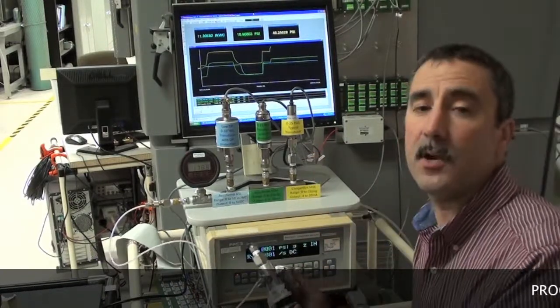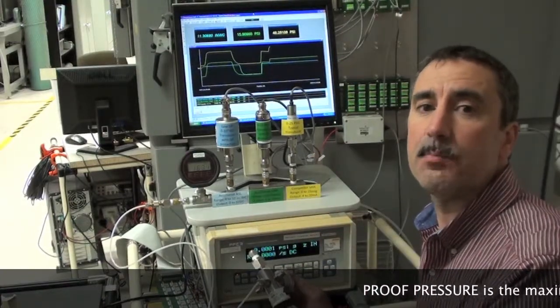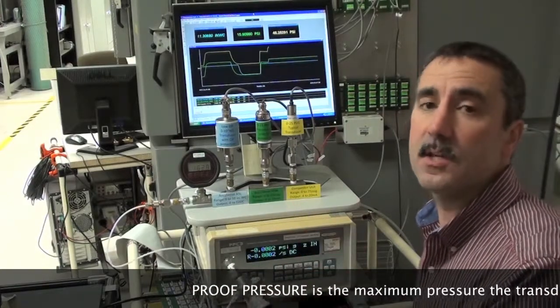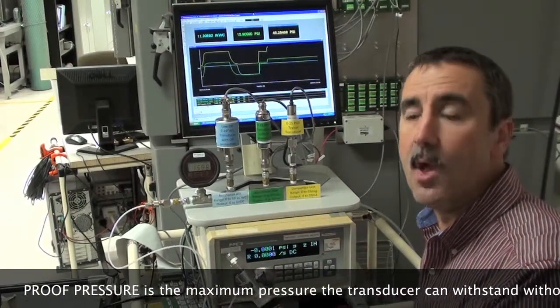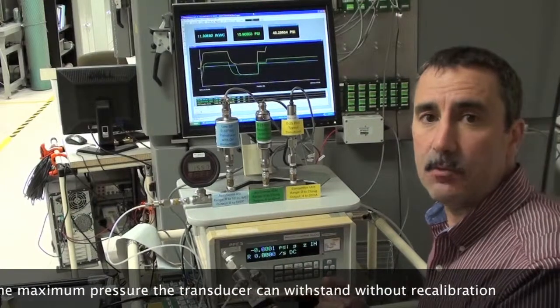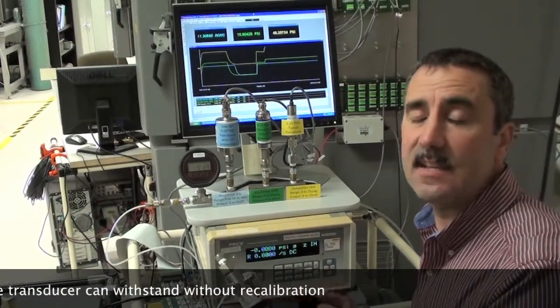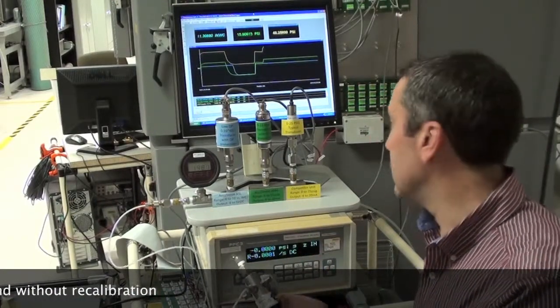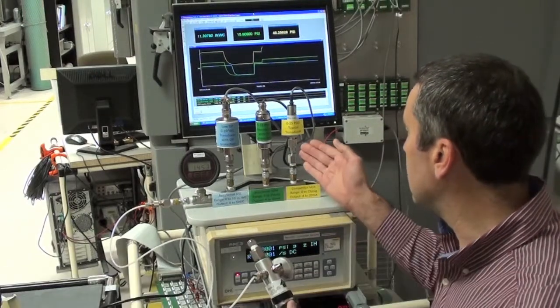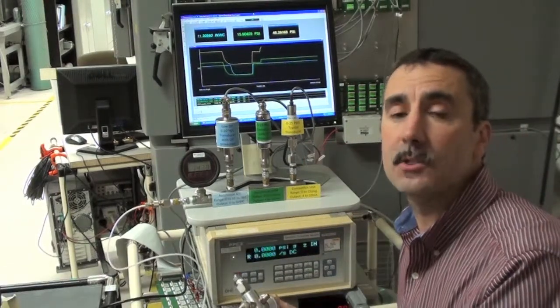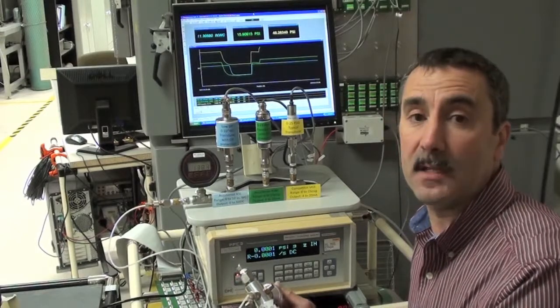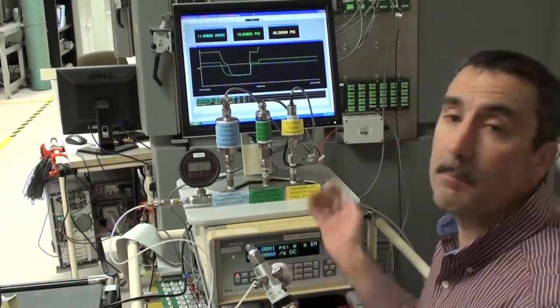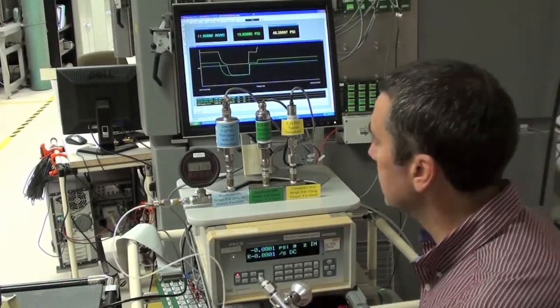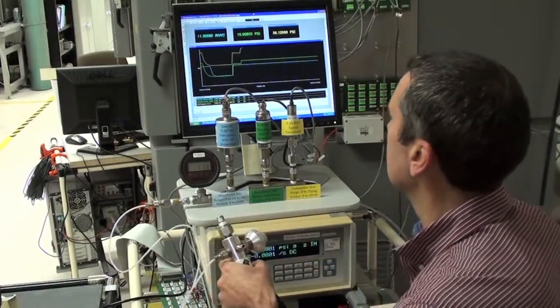Where again, it's proof pressure. Proof pressure is the maximum pressure that you can subject the device to without it needing to be recalibrated. So it's not significantly affecting its accuracy. Where a proof pressure rating on this typical transducer may be 2 times its full scale or 3 times at best its full scale. These offer much higher proof pressure ratings. Vent it.